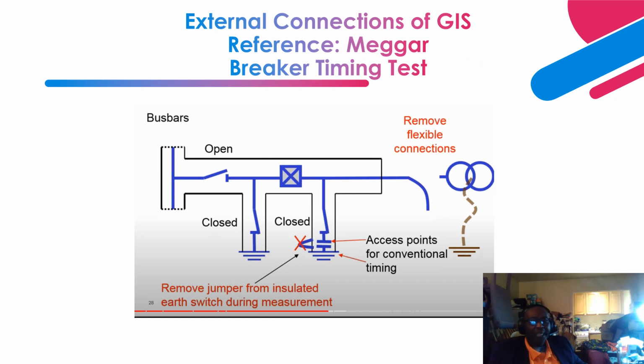Another test is the breaker timing test. Like I indicated, because the GIS is complicated equipment, there are ways and means that have been developed to perform quite close to accurate testing on the GIS. So we have a circuit breaker. This is the line side, this is the bus side. Then we have an external connection.